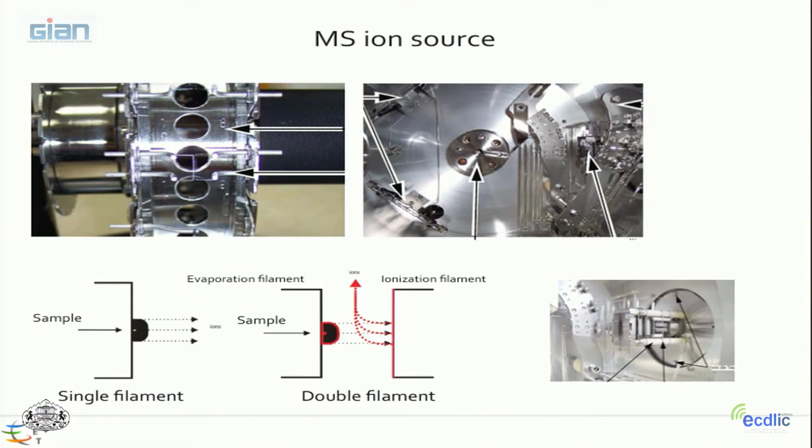It's very easy to change and very easy to clean compared to the old machine, which was a nightmare. Inside you have several lenses, and the ability of the mass spectrometer is to focus the signal correctly. It's like when you focus light with a magnifier, exactly the same process, but with an ion beam instead of a photon beam, and you play with lenses.